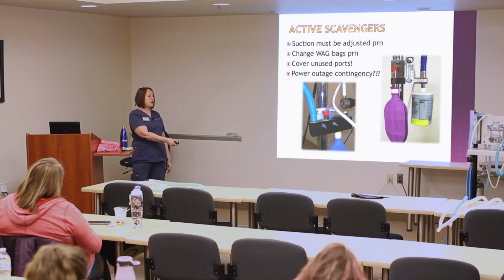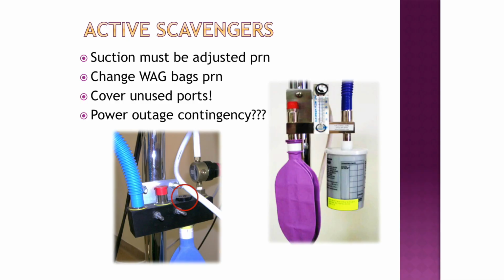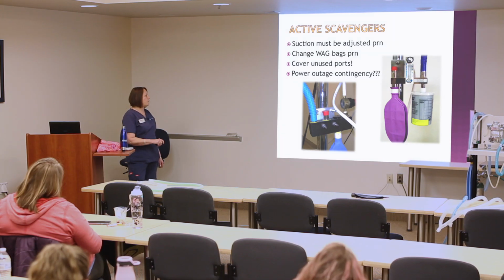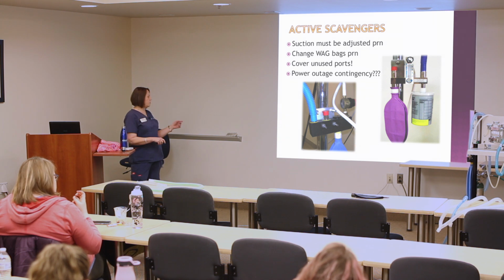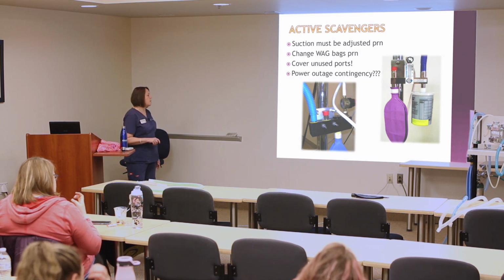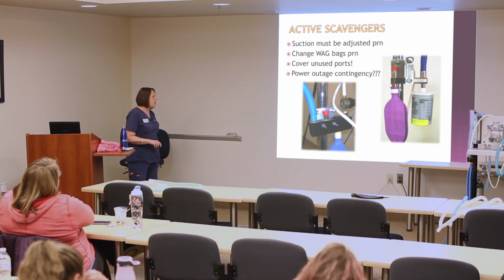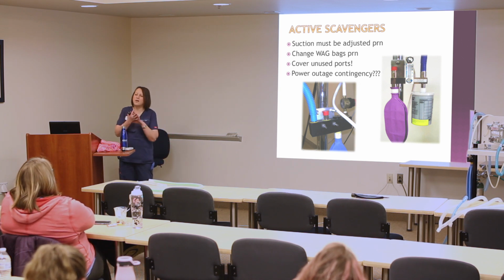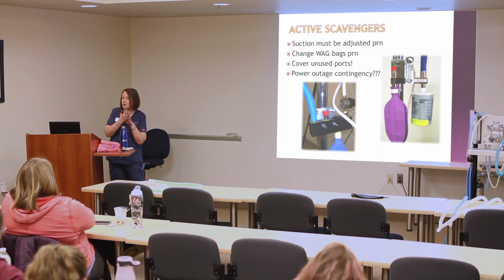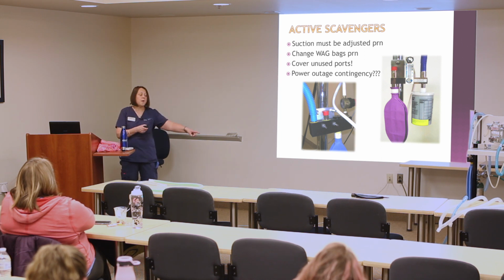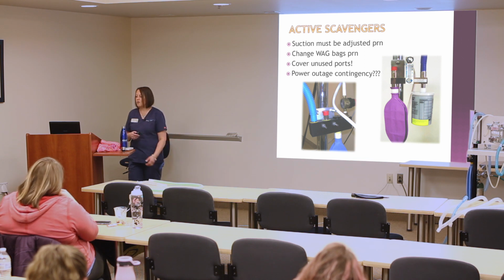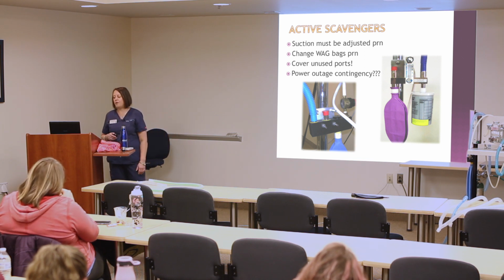Because if you go gangbusters and say, I'm going to empty this bag, all of it right now, you watch your bag down here get really full, and you overfill it. You see these little holes right here. When this is overfull, the gases in this bag come out of this hole right here. So you've just pushed those waste anesthetic gases back into your room. So be very careful. Make sure that your machine is always hooked up to the active scavenger interface, the unused ports are capped, and that you wait for these active scavengers to catch up when you're emptying your patient's rebreathing bag, so that you're not overburdening the blue bags down bottom. I do change them twice a year because they dry rot.